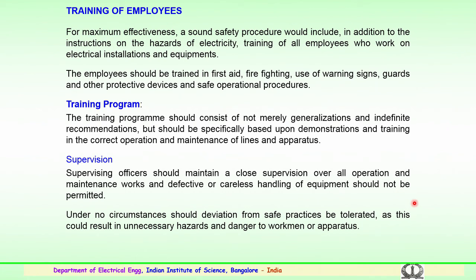So, the necessary training program should be conducted, which should consist of not merely generalization and indefinite recommendations. It should be specifically based upon demonstration and training in the correct operation and maintenance of the transmission line, the equipment in the substation and the apparatus which the person could come in contact with. So, the supervising officers should maintain very close watch on the operations and maintenance works and see that any defective or damaged equipment or careless handling of the equipment is not permitted at the site. Under no circumstances should deviation from the safe practices be tolerated, as this could result in unnecessary hazards and danger to the workman or the apparatus being used.